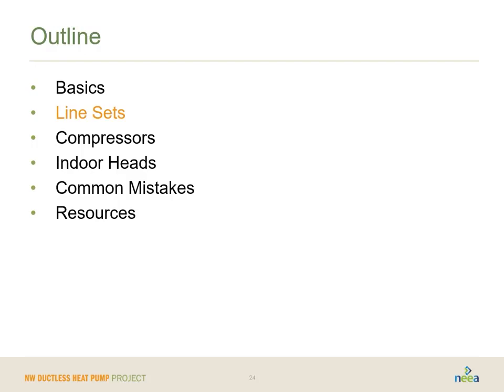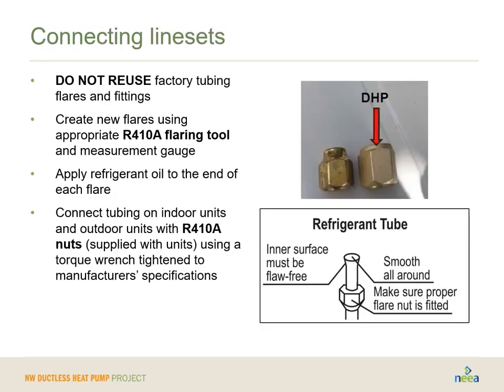The line sets themselves, or the refrigerant lines. So connecting line sets. Remember I mentioned, don't use the factory tubing flares and the factory fittings. They're really not designed for the pressures and the rigor that is necessary for an operating system. They're really there for shipping. So you want to create new flares using that R410A flaring tool that I mentioned. You would apply refrigerant oil to the end of each flare. And remember, this is one of the reasons why we want you to have specific equipment just for working with R410A. And then you want to connect the tubing on the indoor and outdoor units with nuts.